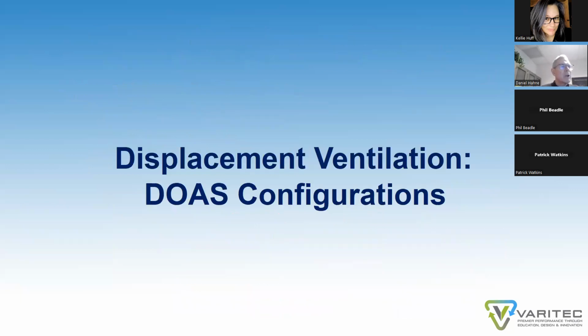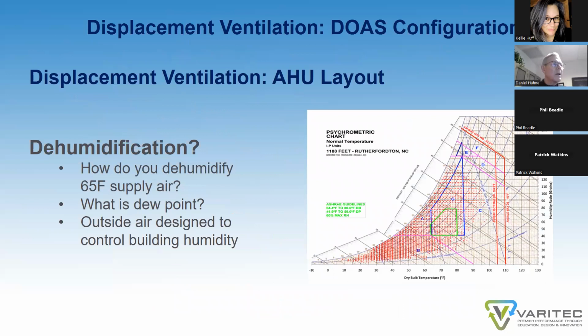So lastly, we're going to look at the airside component again and what is involved in the designing and layout of displacement ventilation 100% outside air units. First of all, again, I'm going to go back to the point that we need to make sure that when you're designing to a 65-degree supply air temperature, you're actually providing air at a low enough dew point to control humidity in the building. Consequently, the chill water coil of the DOAS needs to be designed so that it achieves low enough dew point to adequately control humidity within the space.